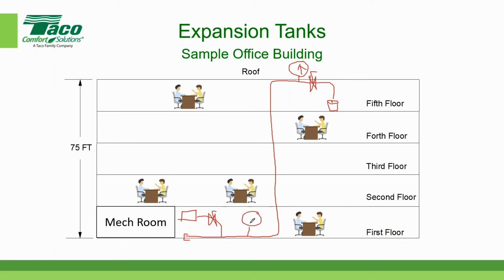So Brett, while I'm chatting here, did anybody come up with an answer? Okay, Chris and Daniel are correct, already said 0. The pressure at the top of the piping system would be 0 pounds per square inch gauge, PSIG. And the pressure at the bottom, I have 32.46 PSIG at 75 feet. Anyways, that's for the bottom.